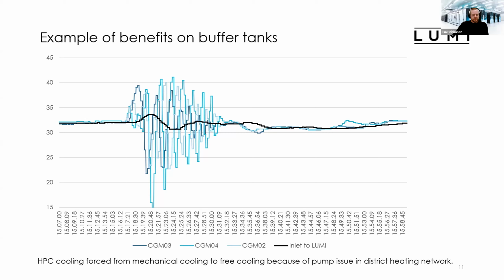So in this case, actually, this HPC cooling was forced from mechanical cooling to free cooling because we had a pump issue on the district heating network. So the heat from the heat pumps couldn't be transferred anymore to the district heating network.